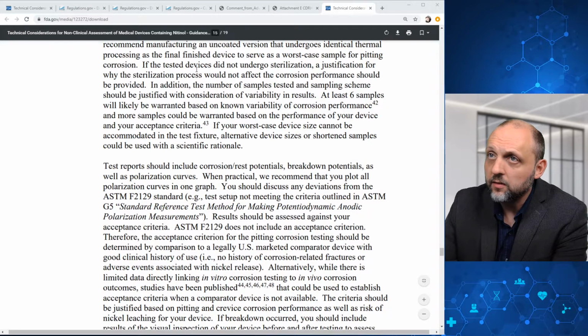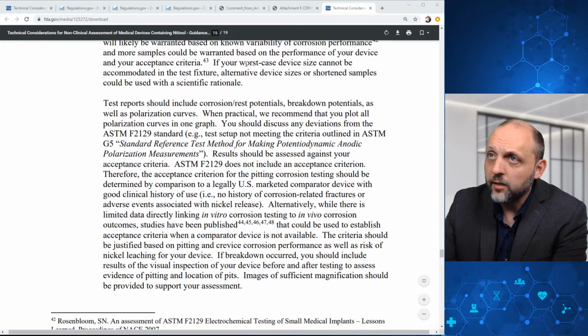If the tested device did not undergo sterilization, a justification for why should be provided. And in addition, the number of samples tested and sampling scheme should be justified with consideration of variability in results. FDA says at least 6 samples will likely be warranted based on known variability. That's a minimum, not a recommended sample size. Here, FDA notes that if your worst case device size cannot be accommodated in the test fixture, then alternative device sizes could be used with a rationale.